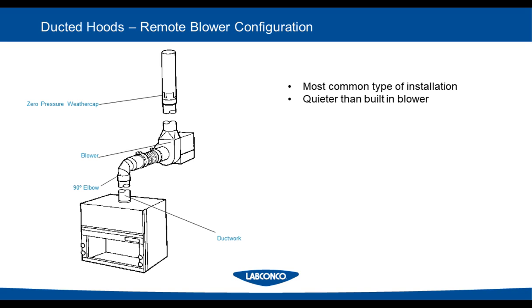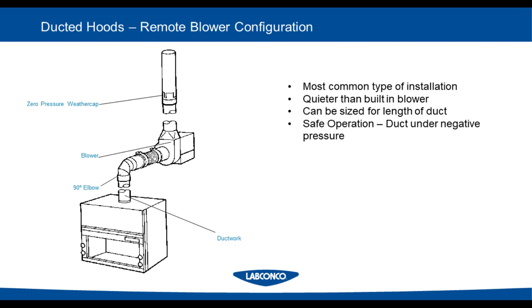This also allows it to be a little bit quieter than typical because, as I've said, it's far away from the hood. Another aspect of the remote blower is that it can be sized for duct length. This includes the total length of the duct, the 90-degree bends, or any other differences in your mechanical system. The benefit here is that no matter what you have, this can be properly sized for a blower that's going to work for your individual fume hood setup.